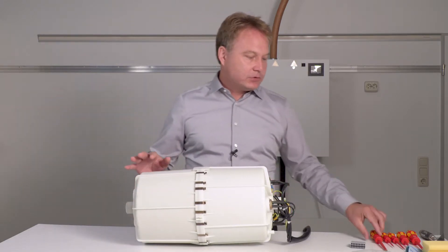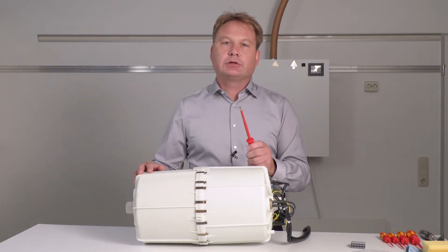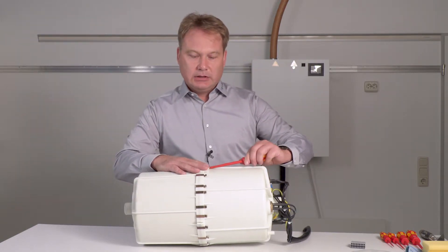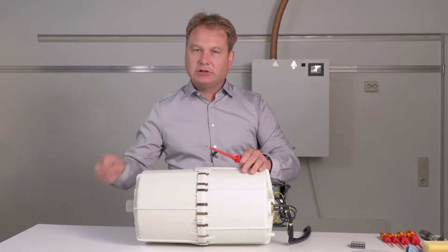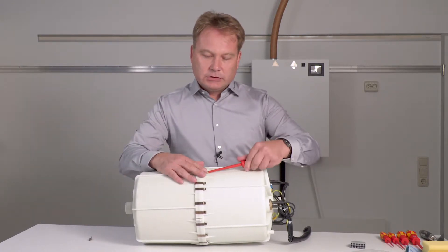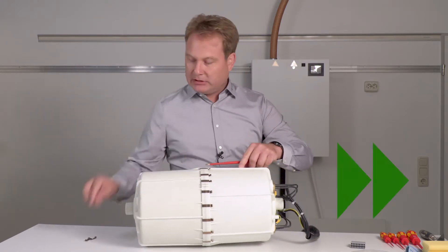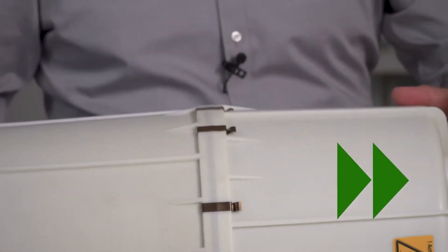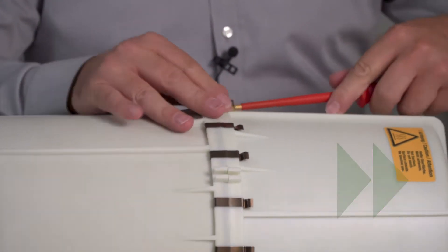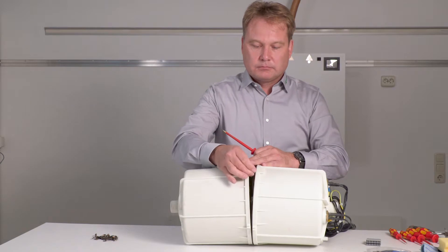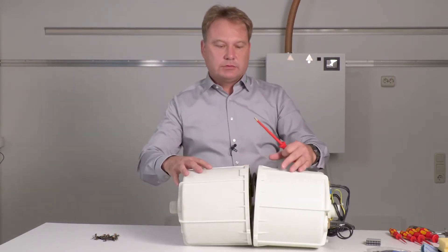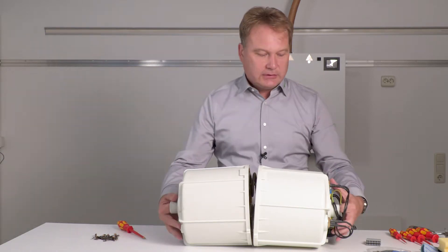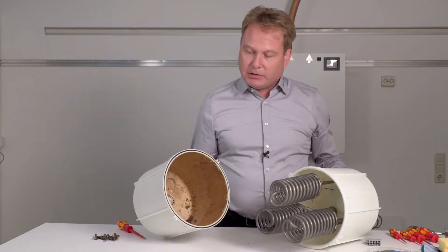For disassembly, we use a standard slotted screwdriver. Lift under the clamps. Just hold on to the clamps a little so that they don't jump out, and go all around. You can see the steam cylinder separating. Now you can pull the two halves apart.